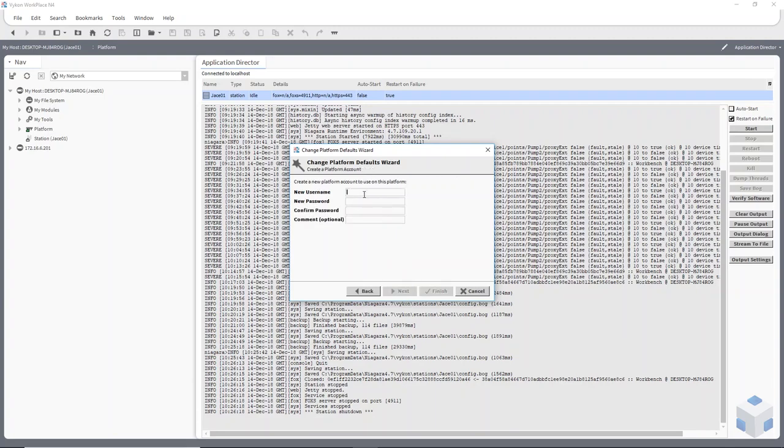And now the platform password I need to change. I'll just call this Tridium 1. Check that your password matches. Okay, so it's telling me a summary of what's going to happen. It's going to be removing the default Tridium account, and adding my new one here. So click finish. That's before I even get to the commissioning wizard. I think it was N4.6 that changed this. This bit's been added; it used to be part of the commissioning wizard before.